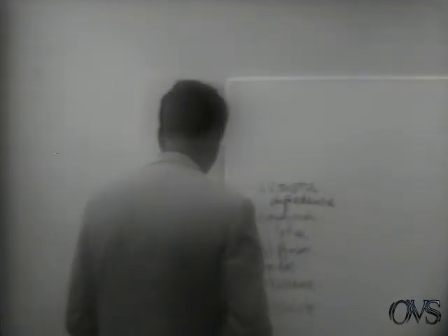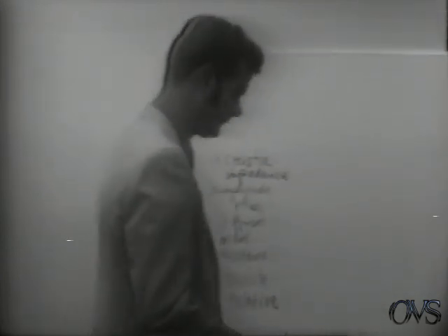Absolute acoustic impedance evaluates the ability of sound to transfer from the outer to inner ear via the middle ear. This entails measuring middle ear pressure, the ear cavity volume, and acoustic impedance in the plane of the eardrum. Relative acoustic impedance is concerned with the effect of the middle ear muscles on sound transmission. The reflex which results from the contractions of the intra-aural muscles is measured.